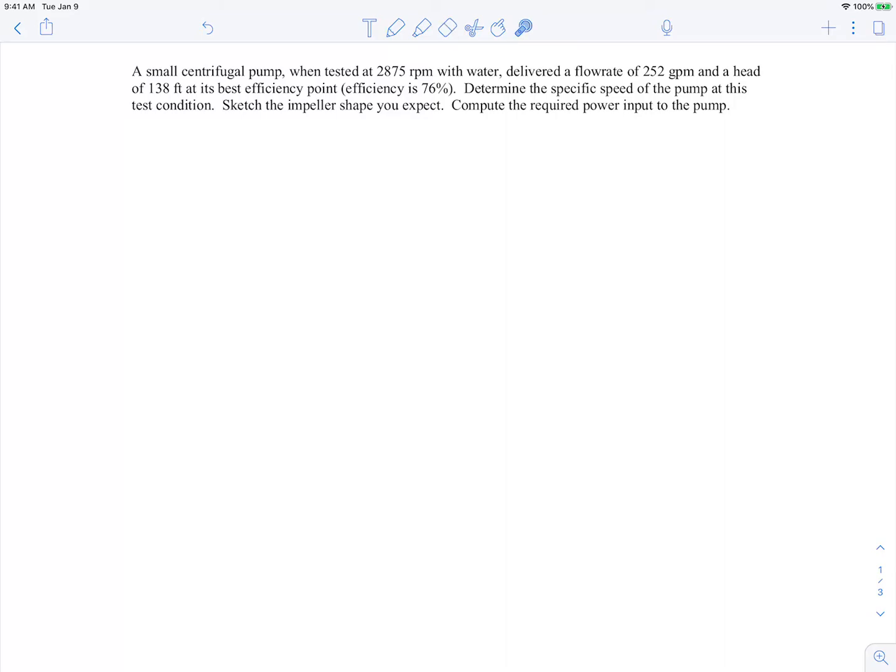In this example, we have a centrifugal pump tested at 2875 RPM delivering a flow rate of 252 gallons per minute and a head rise of 138 feet. It's being tested at its best efficiency point, which gives an efficiency of 76%. We're asked to determine the specific speed of the pump, the impeller shape, and the required power input into the pump.